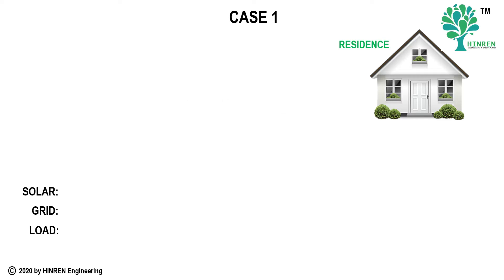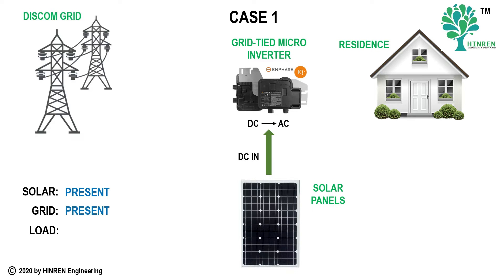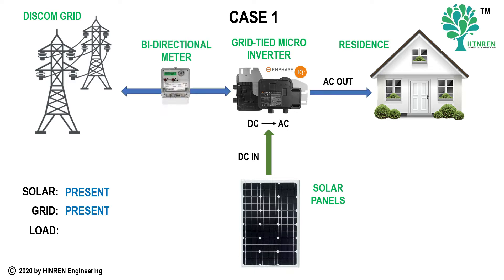In a net metering solar PV system, we have solar panels generating DC power, a grid-tie inverter, and the DISCOM grid. DISCOM is the distribution company responsible for power distribution in the locality, and of course you have the load. Between the inverter and the DISCOM grid, there is a bi-directional meter which records both the energy taken from the grid and the energy given to the grid. This bi-directional meter is used for billing purposes.